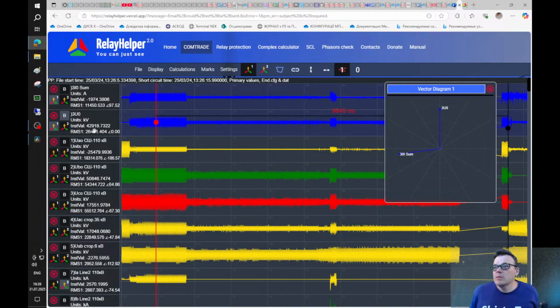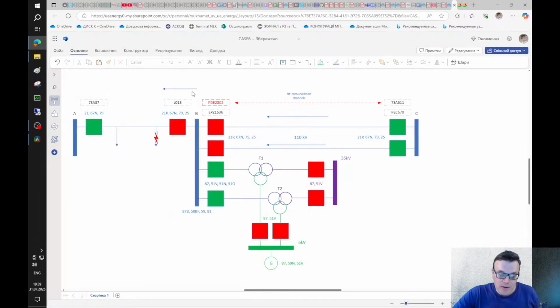I recommend you watch my video, because, as I said earlier, I have heard a lot of arguments about how to determine the direction to the fault, and there is usually some misunderstanding. We can't say that zero sequence power was directed to the fault, because the fault is the source of the zero sequence power. So usually, if we talk about zero sequence power, we should say that it is directed from the fault to the substation. It is very easy to have a misunderstanding with other engineers. That's why I am describing what I want to show and what I want to add.